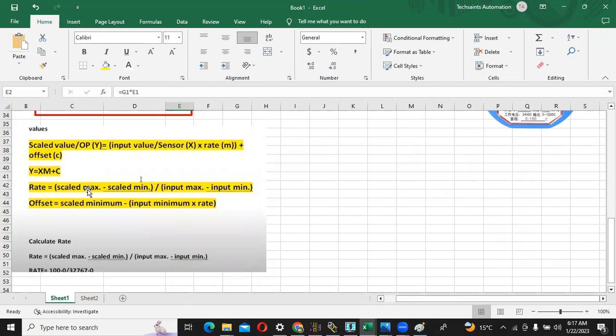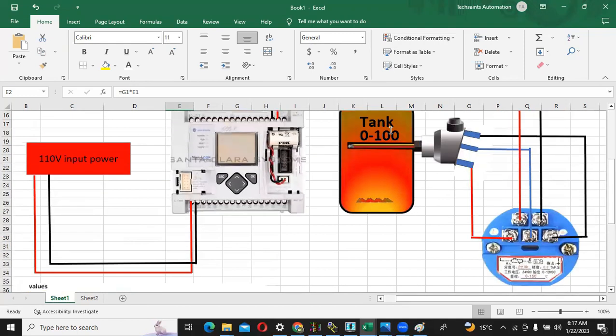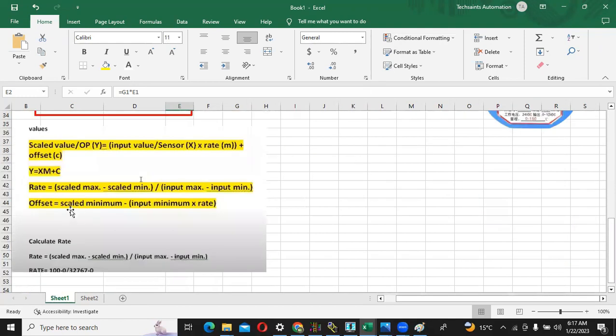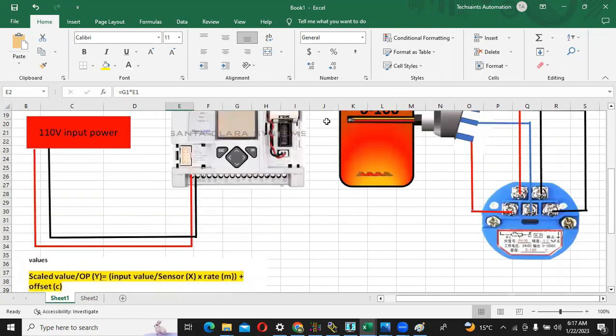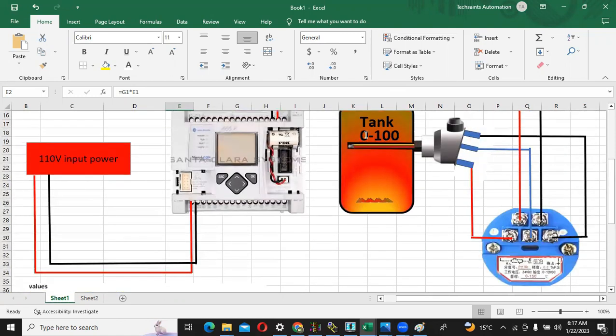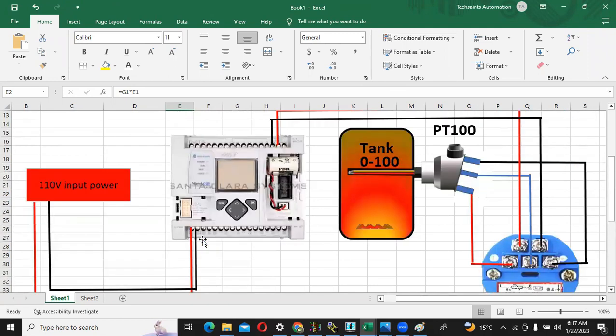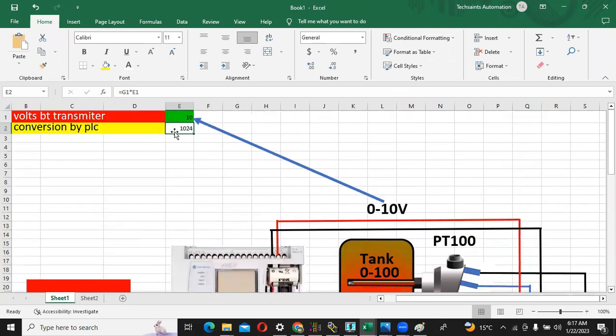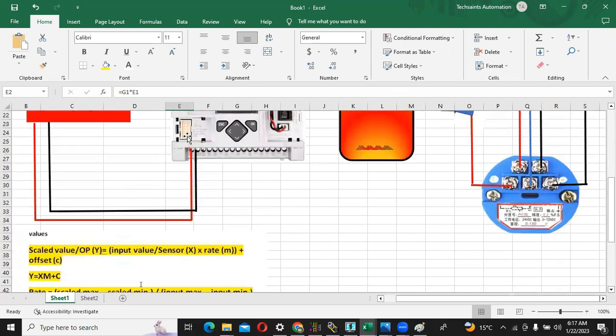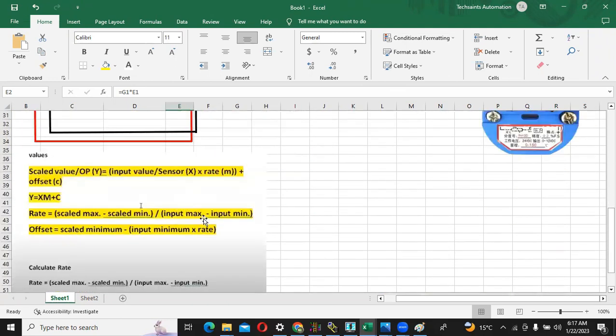Scaled maximum, scaled minimum, input maximum and input minimum. So scaled maximum, the value which I want to scale is 100 degrees centigrade, and my scaled minimum is 0. Input maximum is 1024 and input minimum is 0.